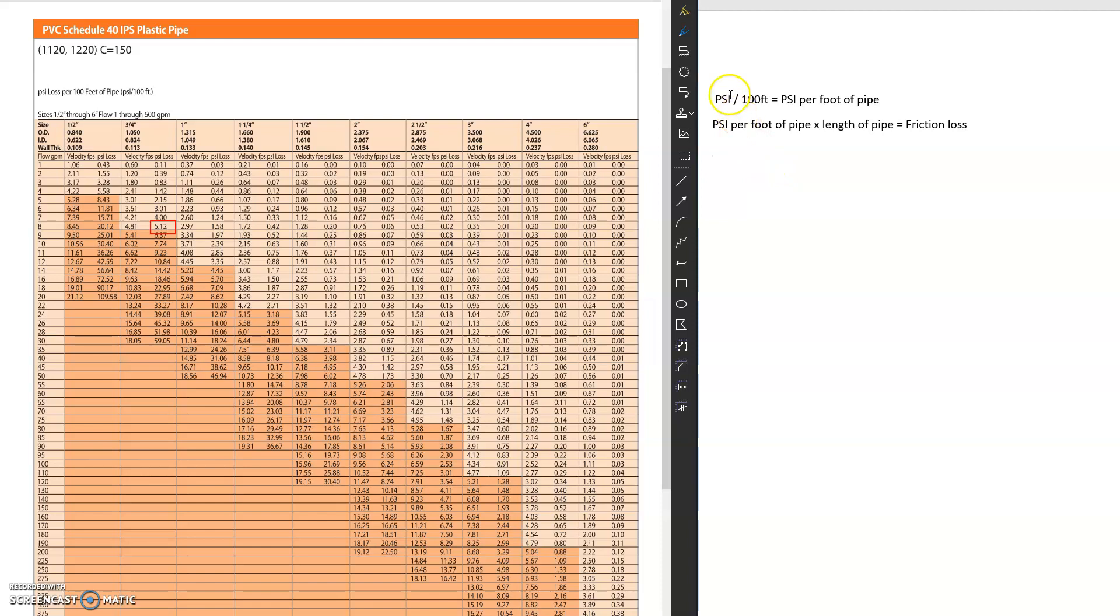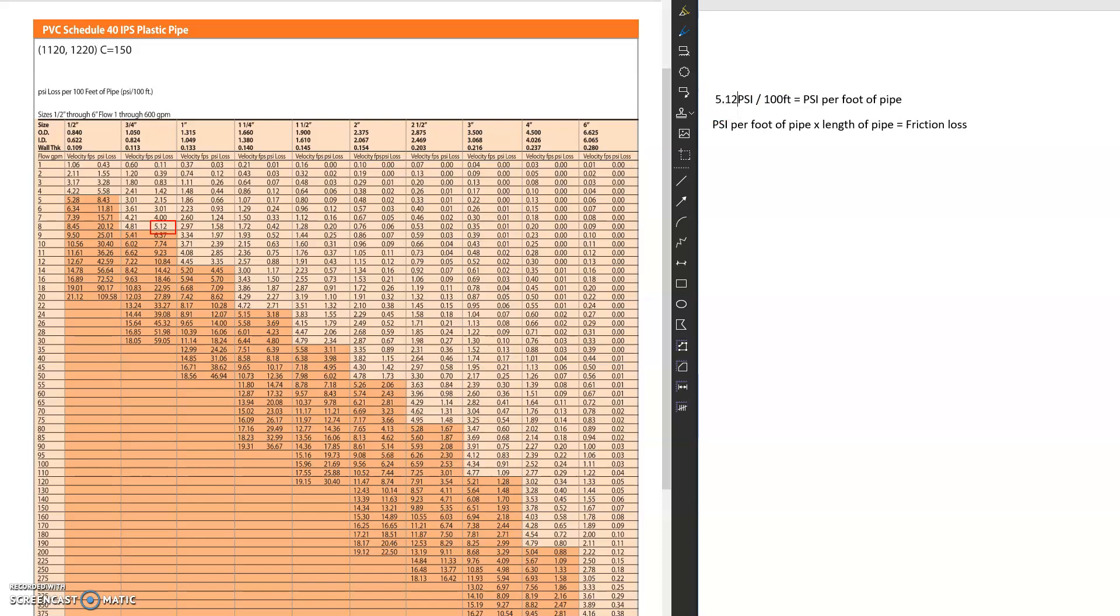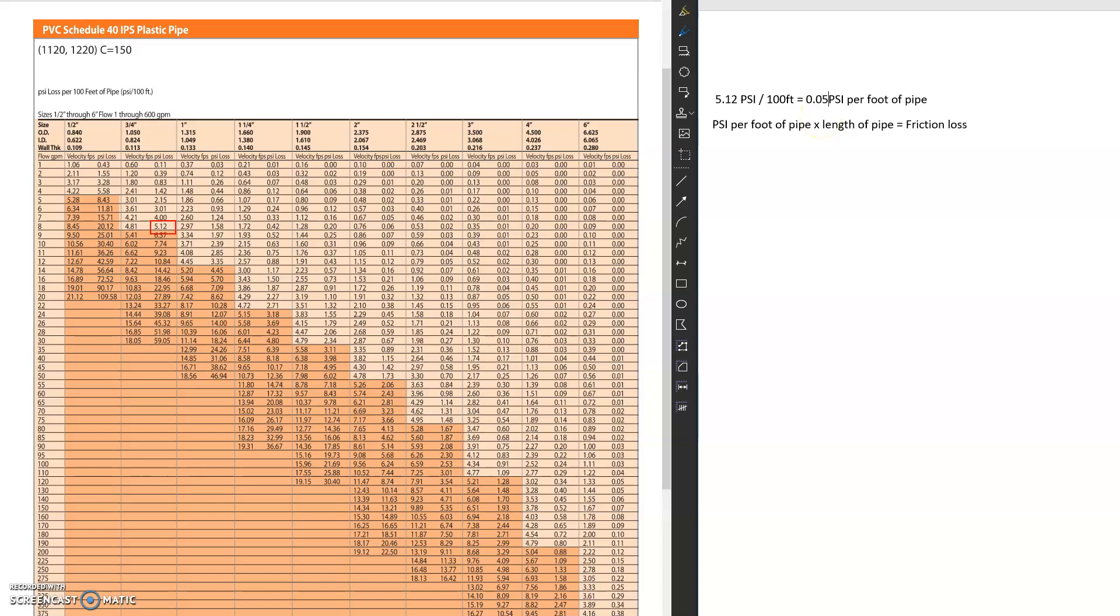So how do I figure this out? Well, first, since it's for 100 feet of pipe, my PSI loss is going to be 5.12. And then I'm going to divide that by 100, which is going to give me the PSI per foot of pipe loss, which is this very low 0.0512 PSI per foot. Now, you know why they multiply it by 100 feet. So it's actual numbers that are easy to register and deal with.